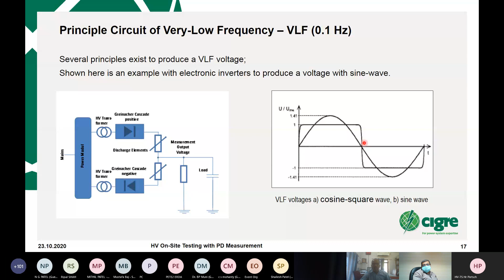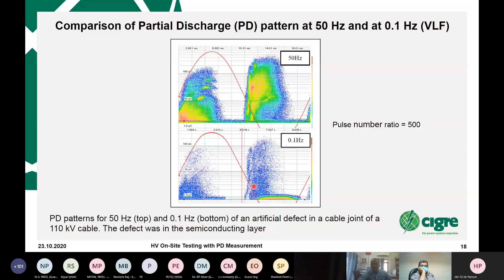As you might see here, I don't want to go into the physical details, and this was not the intention of the brochure. The upper pattern shows the partial discharge pattern, collected over time. Every dot represents one single discharge, shown relative to the applied phase, in this case 50 hertz, and at the bottom 0.1 hertz. So one oscillation is 10 seconds, and here one oscillation is 20 milliseconds. Due to the polarity reversals I mentioned, you have many more PD pulses than at 0.1 hertz. Now you can recognize that it looks quite similar, but it's not similar. And even these defects, or whatever they are, could be artificial or could come from the surroundings. So you see it's very tricky, and only experts who know the technology, especially the object you test, how it's built and designed, can make an analysis of whether this is harmful or not.